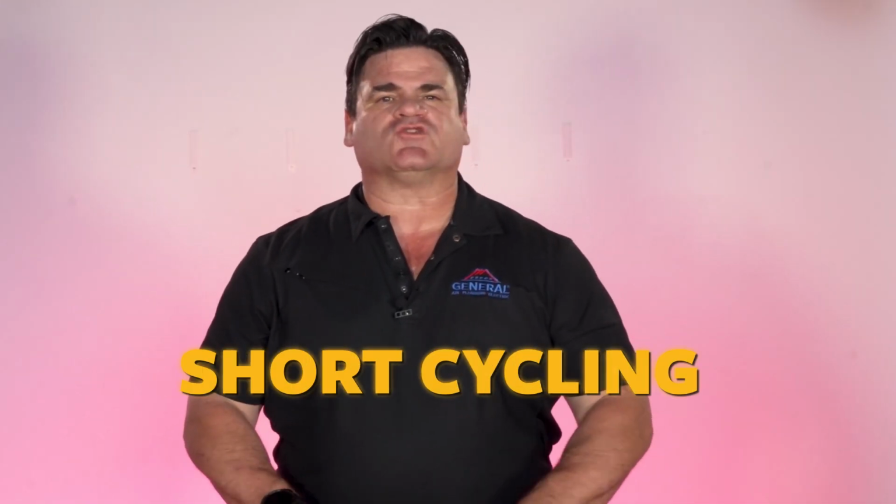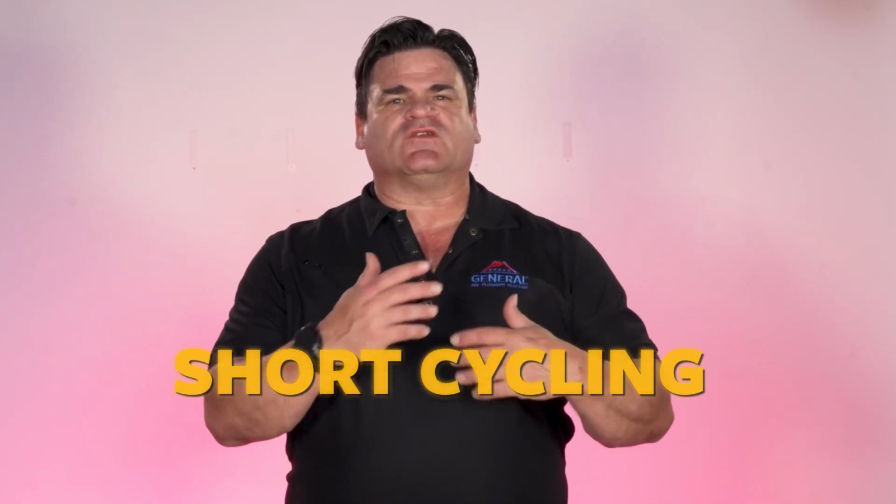Okay, hey, Patrick, then I should have a bigger system. We'll get that humidity out of the air quicker. No, you won't. Your system will do something we call short cycling. It pulls it out quickly, drops the temperature quickly, but it hasn't properly pulled the moisture out of the air. So your system short cycles. It runs, then it shuts off. Then it runs, and then it shuts off. It doesn't complete a full cycle to properly cool your home and leave you comfortable.